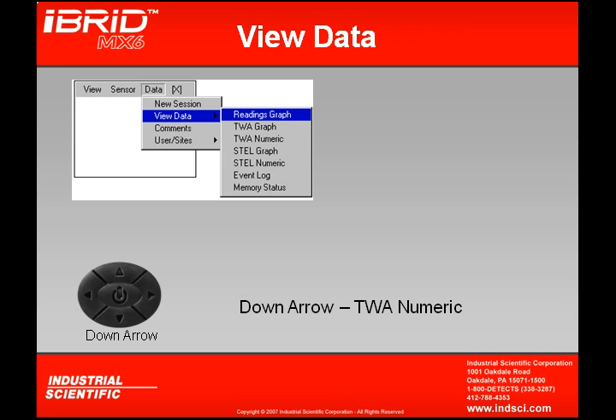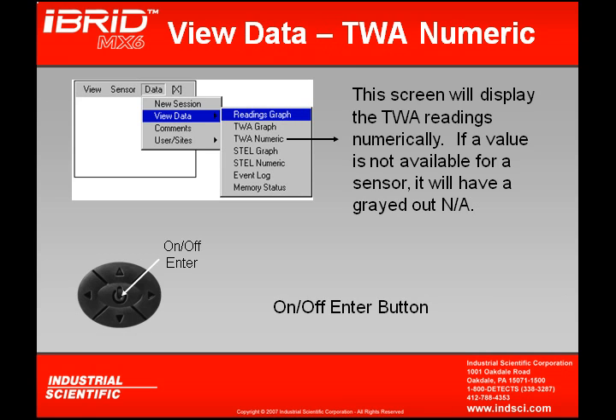If I hit the down arrow from TWA graph, I bring up my next option, which is TWA numeric. TWA numeric will show me the actual time-weighted average readings numerically, but there are a couple gases like oxygen and combustible which do not tabulate for time-weighted average, and therefore grayed out in their space will be the letters NA.